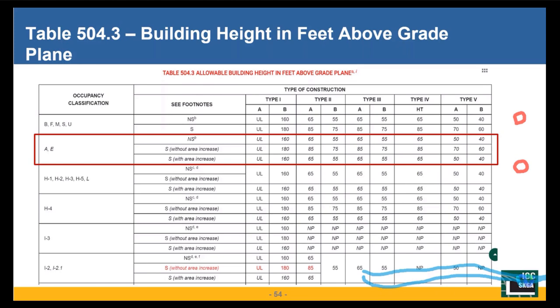So for A and E, when we talk about sprinkler system, it will be sprinkler system installed in accordance with section 903.3.1.1, which is the full-on sprinkler system, the best sprinkler system there is, that will require sprinklers in concealed spaces and everything else. Whereas 13R and 13D is less. That will be covered in the Chapter 9 webinar.